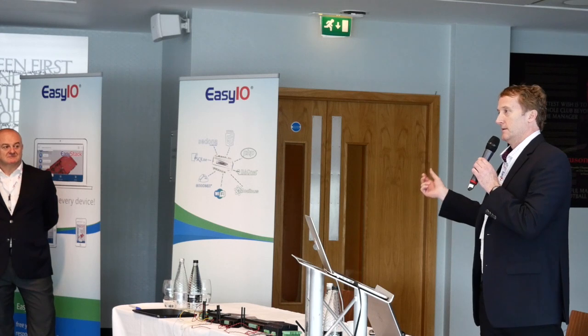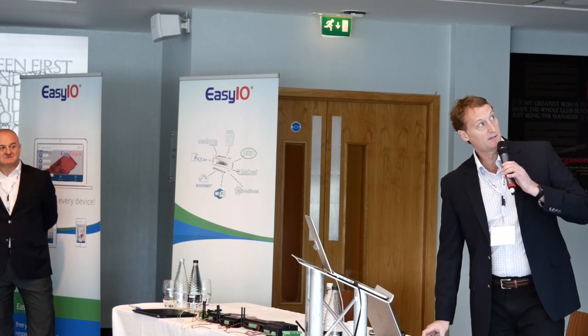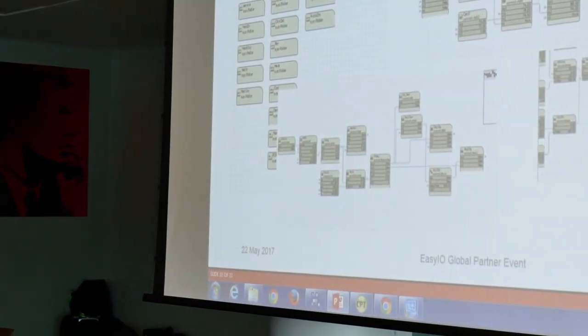So it's not like, well, what's the dead band, 20 CFM? Well, that might be good if you're down at minimum. But when you're up at maximum flow set point, which might be 2,000 CFM, maybe I want my dead band a little bigger. Well, in the logic, that dynamically adjusts based on the setting. And again, easy to understand logic. There's nothing special under the hood here. 90% of this is built with the standard Tridium Sedona kits, right? Those core kits from Control Kit. And that's it.